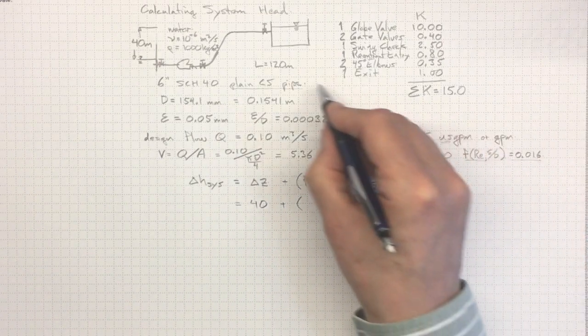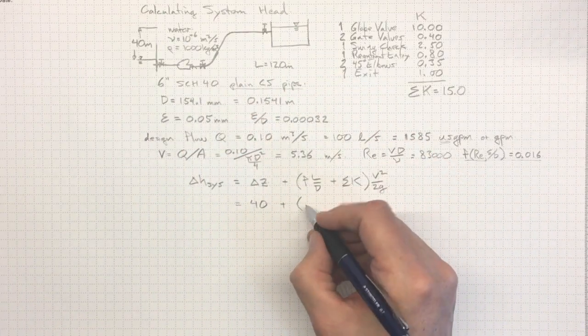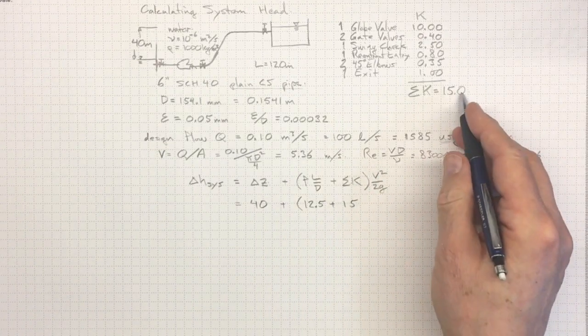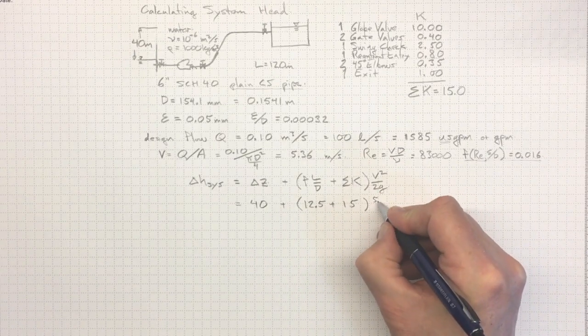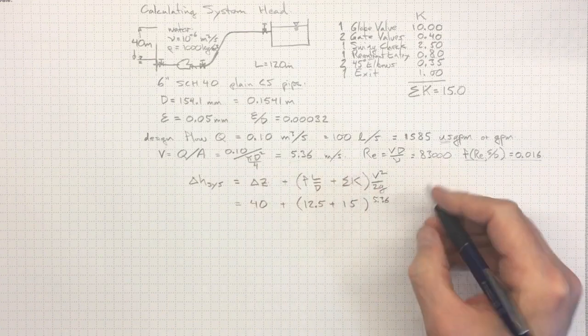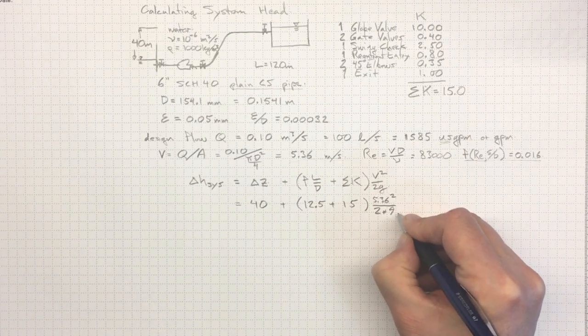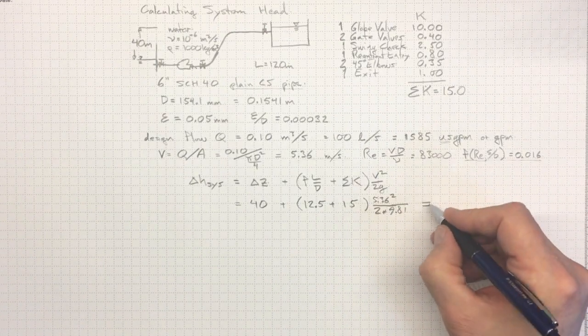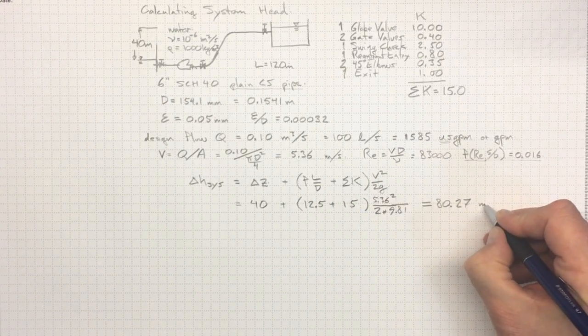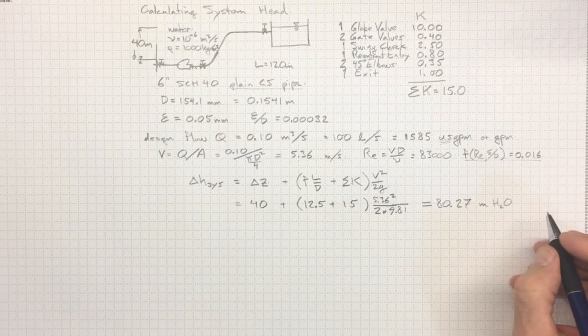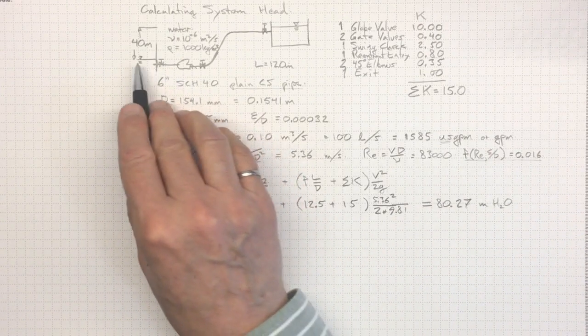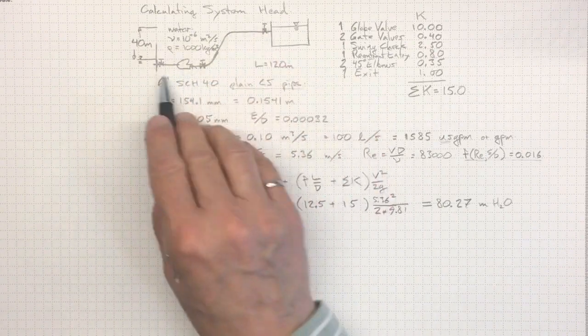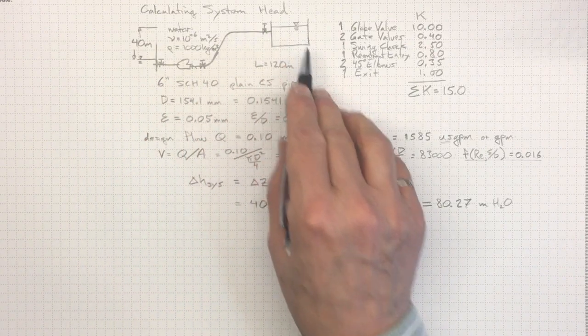So, that'll be equal to 40, plus, if I take F times L divided by D, I'll wind up with 12.5, plus 15, for the sum of the loss coefficients, times V squared 5.36 from up here over 2 times 9.81, the value of G. And if I plug all of that through, I'll wind up with 80.27 meters of water as the head rise that I would need across that pump in order to overcome the 40 meters of elevation difference, the friction along the pipe walls, and all the minor losses in each of these little fittings along the way.